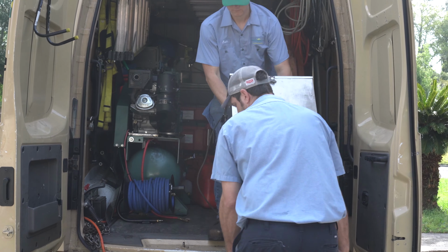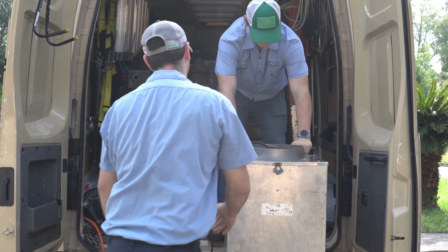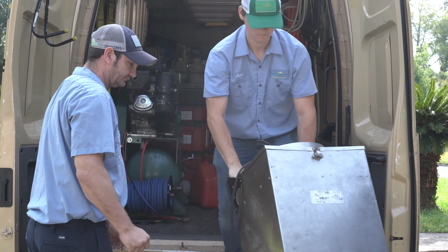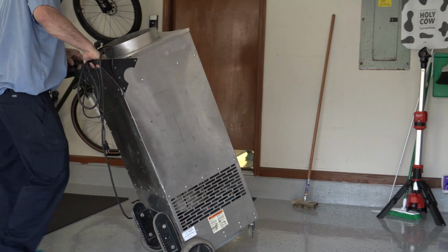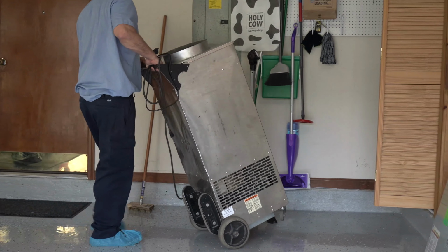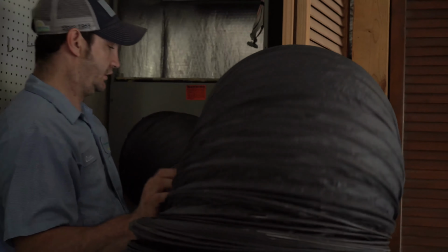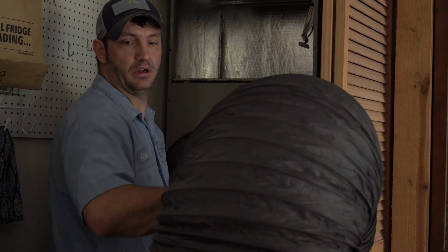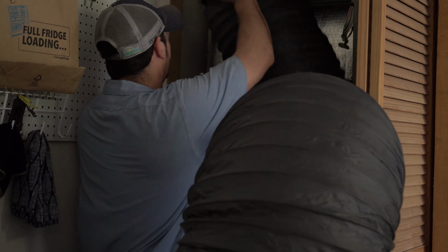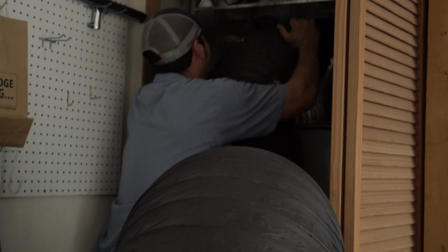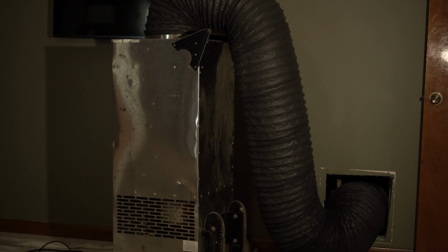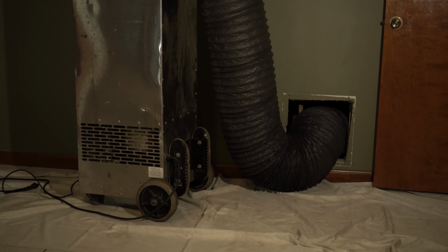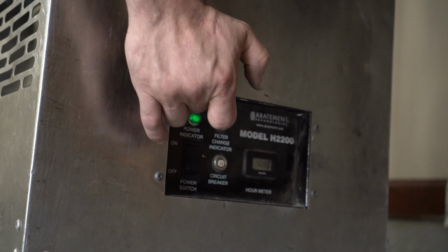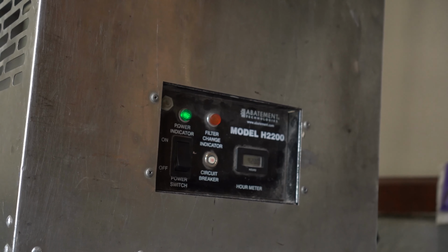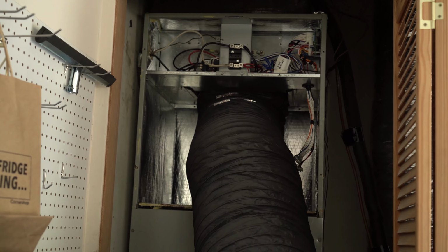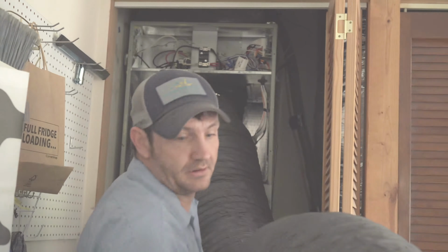The air handler style and duct configuration will determine how you set up your HEPA vacuum. A good example of this is if you are connecting to a Trane TAM style air handler with the blower in the bottom. You will need to access the duct plenum directly above the air handler or the first mixing box if the plenum is flexed. To clean the return, you may also need to hook your HEPA vacuum up to one of the returns inside the house instead of at the plenum. Look at the unit configuration during your job overview to ensure that you will get the maximum suction during the duct cleaning process.